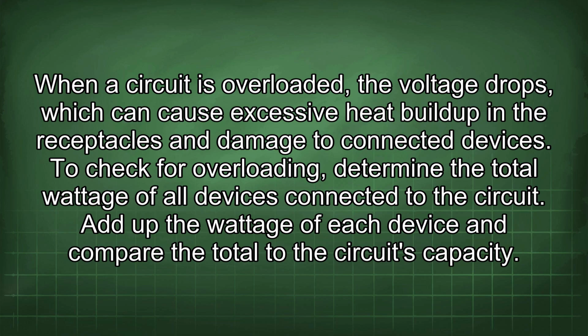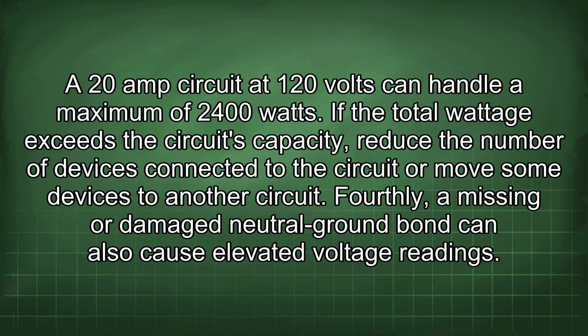Add up the wattage of each device and compare the total to the circuit's capacity. A 20 amp circuit at 120 volts can handle a maximum of 2400 watts. If the total wattage exceeds the circuit's capacity, reduce the number of devices connected to the circuit or move some devices to another circuit. Fourthly, a missing or damaged neutral ground bond can also cause elevated voltage readings.